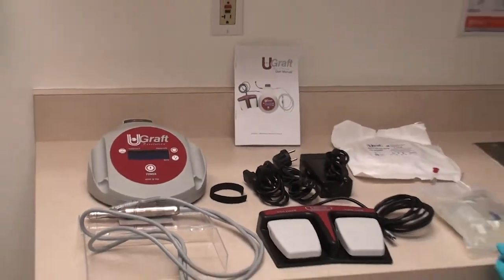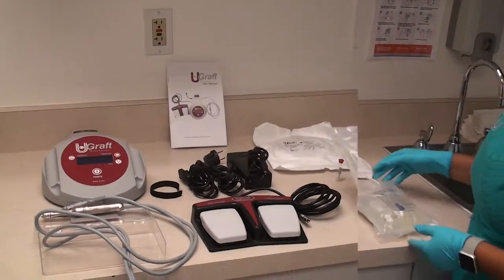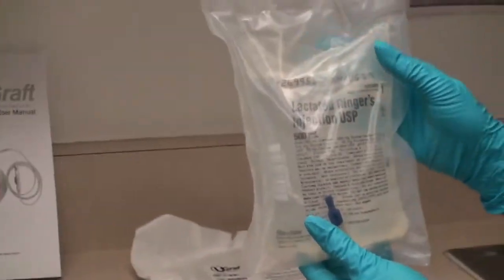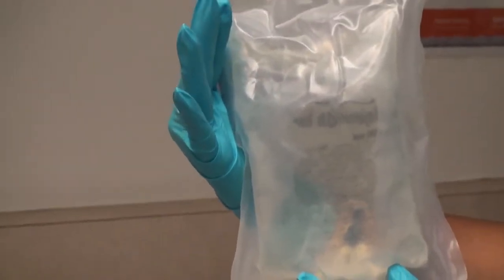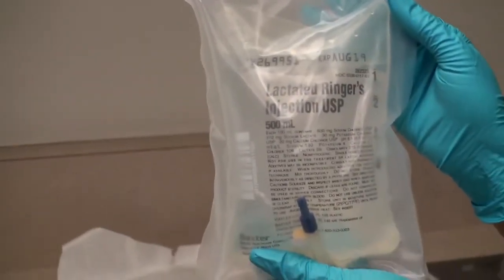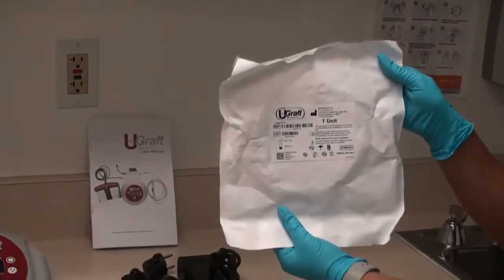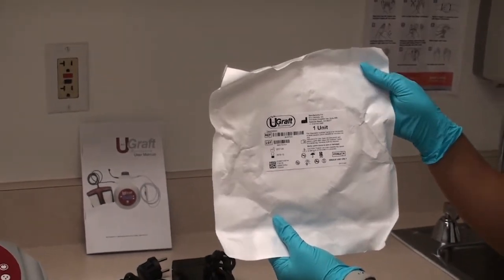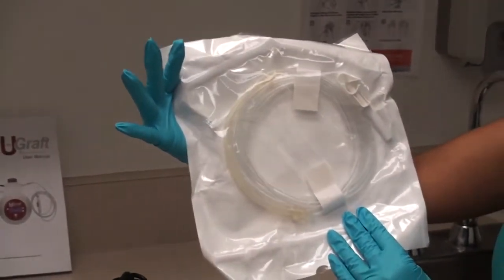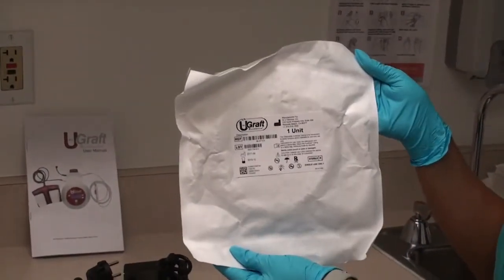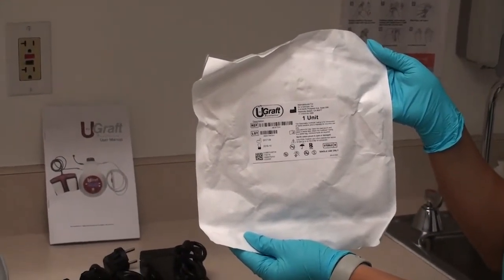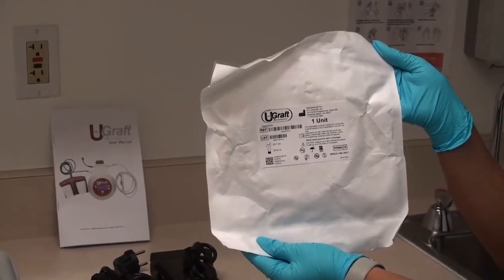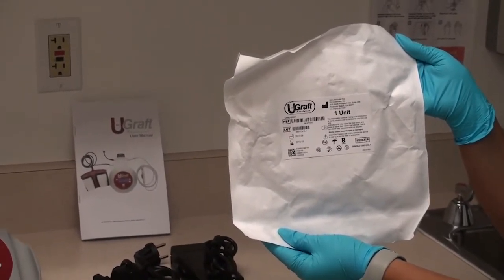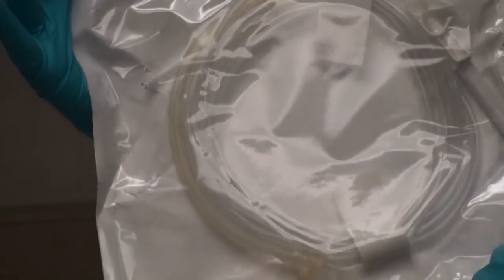3 consumables are needed to operate the Dr.UGraft system. Number 1 is the Physiologic Fluid Bag. It is the same type of bag that you would use to administer IV fluid, so it is off the shelf. There is nothing special about it. Second is the Dr.UGraft tubing system, which comes pre-packed and already sterilized in a sealed package. Check to ensure that the package is unbroken before opening it, otherwise it is not to be used. This tubing system connects the Physiologic Fluid Bag to the fluid port on the handpiece. It is specially made to work with the Dr.UGraft hair transplant system.